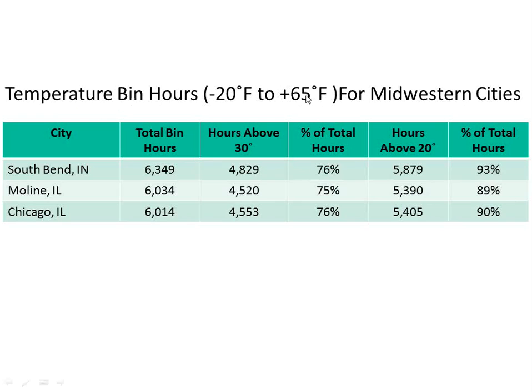So below 65 degrees outside. Of the days when it's below 65, there's 6,000 hours in Chicago that we would have in that scenario. So 6,000 hours below 65, that means 2,760 hours above 65. So it is definitively a heating-dominated climate. And typically we're designing for -3, -4, -5 degrees outdoor air temperature in the Chicago area. I know some of you guys do -10. The new energy codes don't allow your load calcs to use -10, but if you want to think about it for this discussion, that's fine too.